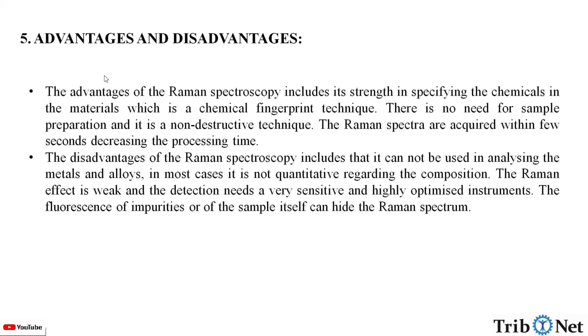The advantages of Raman spectroscopy include its strength in specifying chemicals in a material — it is a chemical fingerprint technique — there is no need for sample preparation, and it is a non-destructive technique. Raman spectra are acquired within a few seconds, decreasing processing time. The disadvantages include that it cannot be used to analyze metals and alloys in most cases, it is not quantitative regarding composition, the Raman effect is weak and detection requires very sensitive and highly optimized instruments, and fluorescence of impurities or of the sample itself can hide the Raman spectrum.